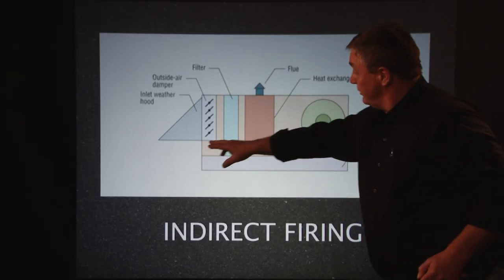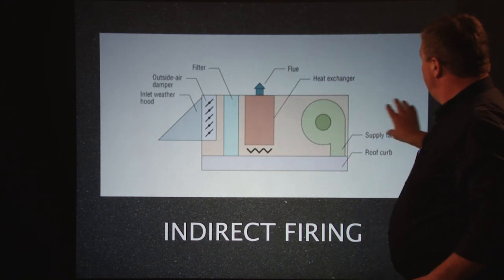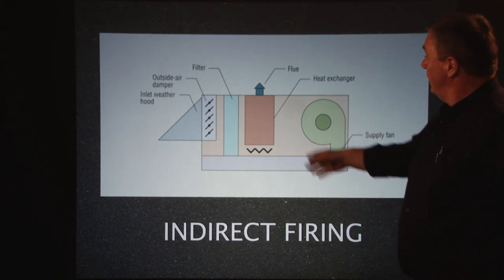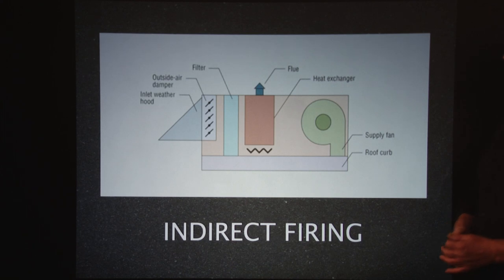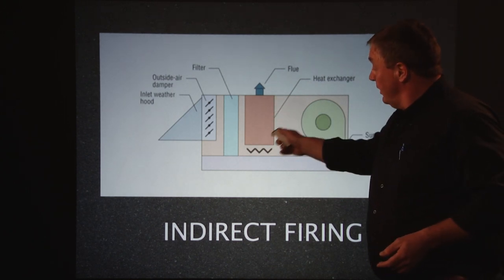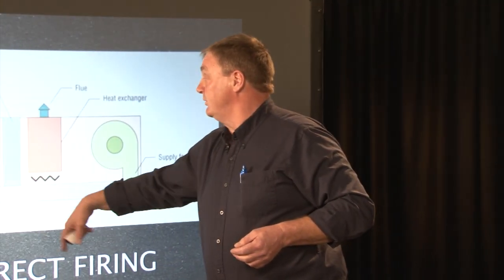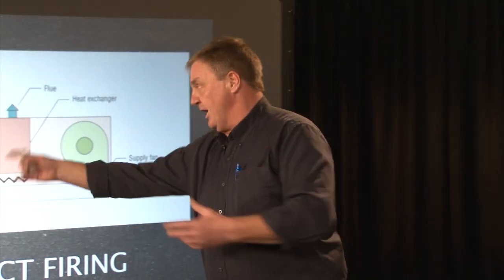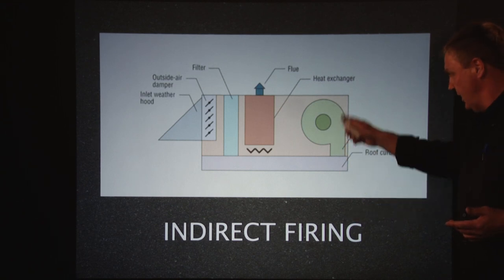Here we have the indirect fire system. The difference is you'll have a heat exchanger. You'll still have the weather hood, the damper, and the filter, with your heat source underneath, passing through a heat exchanger and again through the fan, down through the roof — but these ones will have a flue because the exhaust gases are vented out and away. The inspection part is to see if the heat exchanger is working well, not damaged or blocked, and that the filter's in good condition — a bird hasn't got in and decided to make a nest in front of the heat exchanger, reducing its efficiency.